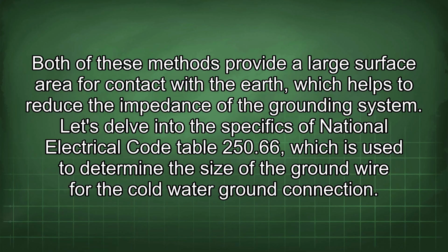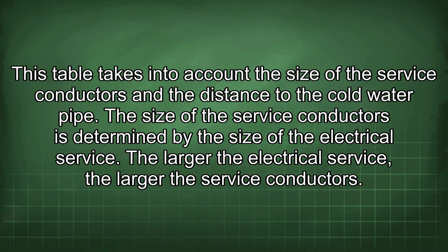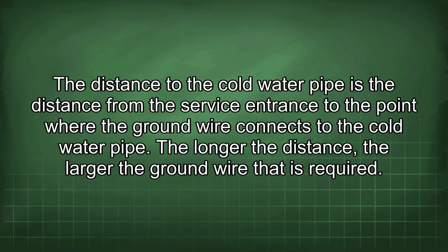Let's delve into the specifics of National Electrical Code Table 250.66, which is used to determine the size of the ground wire for the cold water ground connection. This table takes into account the size of the service conductors and the distance to the cold water pipe. The size of the service conductors is determined by the size of the electrical service. The larger the electrical service, the larger the service conductors. The distance to the cold water pipe is the distance from the service entrance to the point where the ground wire connects to the cold water pipe. The longer the distance, the larger the ground wire that is required.